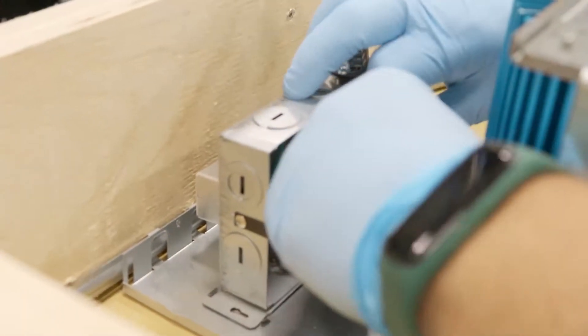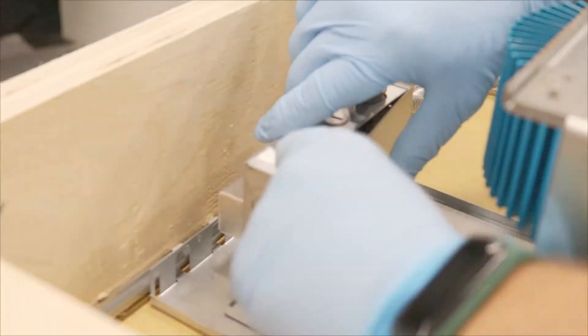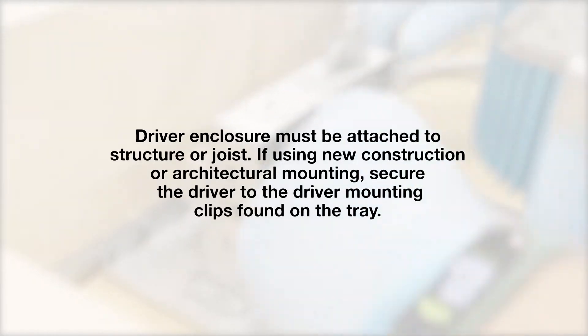Snap the driver box into position on the mounting plate. The door of the driver should be visible from the ceiling opening for the fixture. The driver enclosure must be attached to a structure or joist. If using new construction or architectural mounting, secure the driver to the driver mounting clips found on the tray.